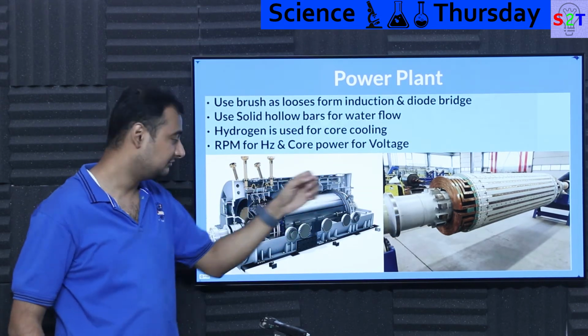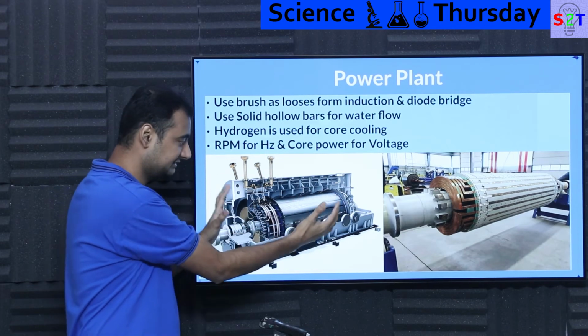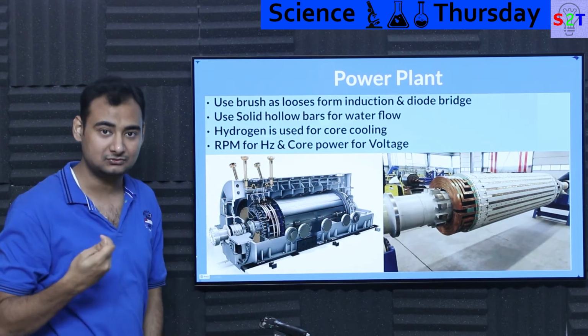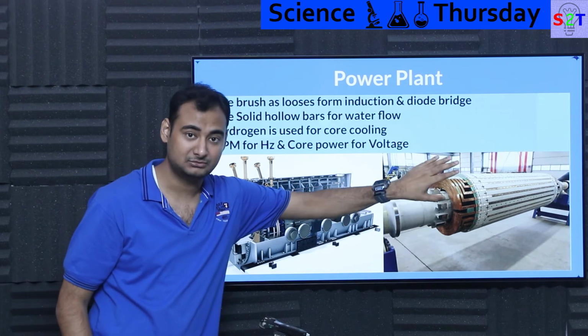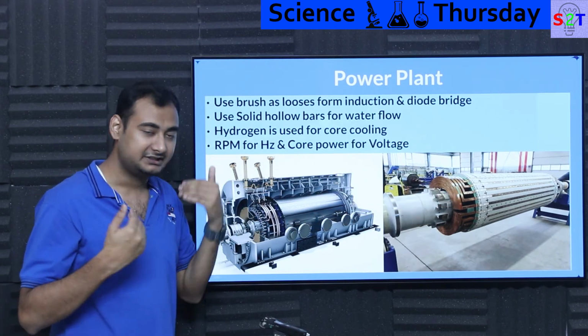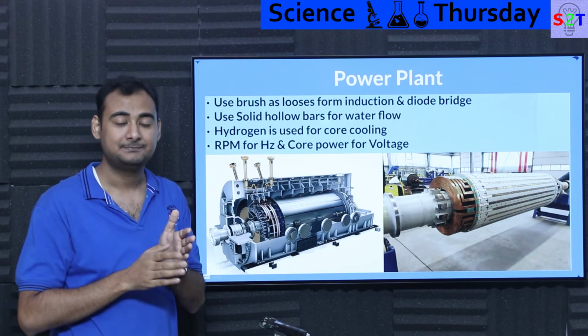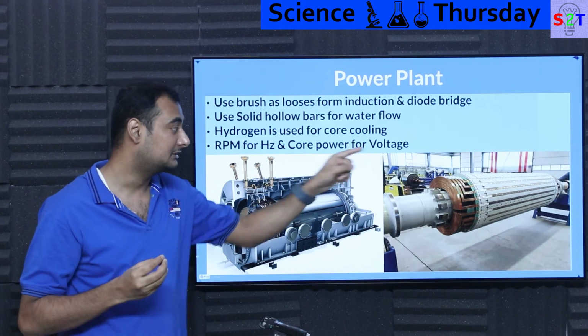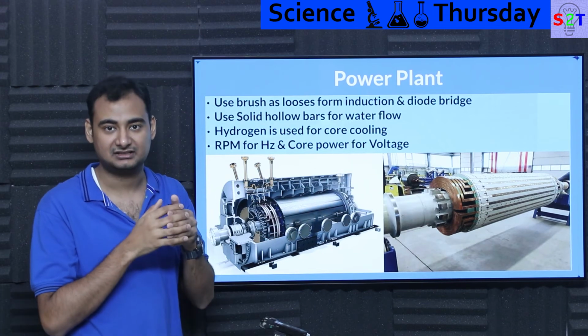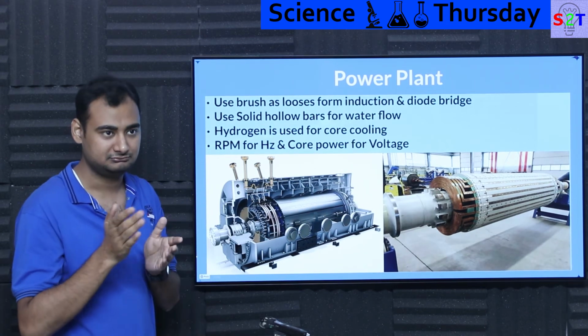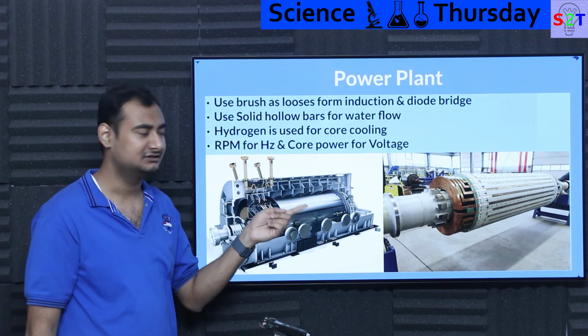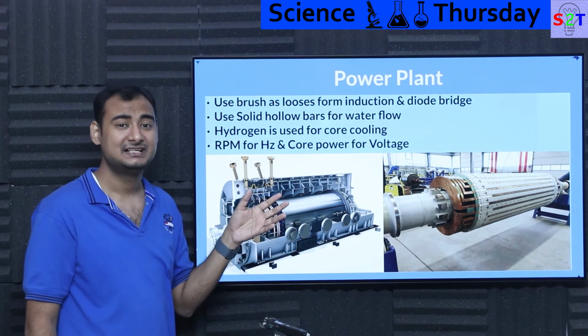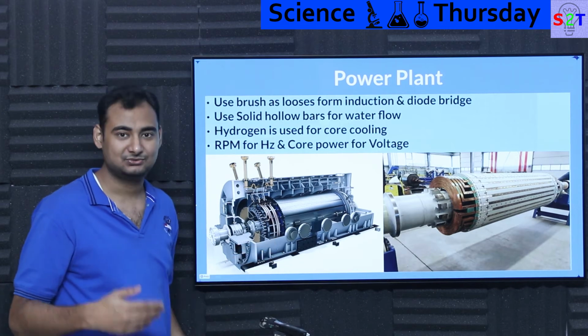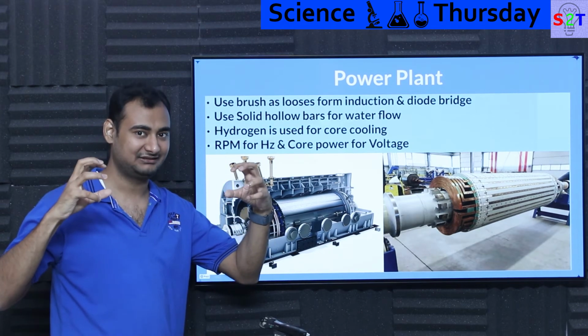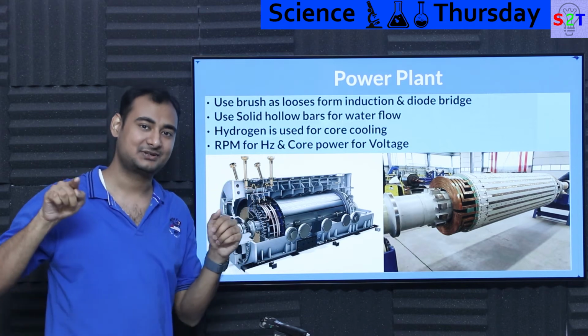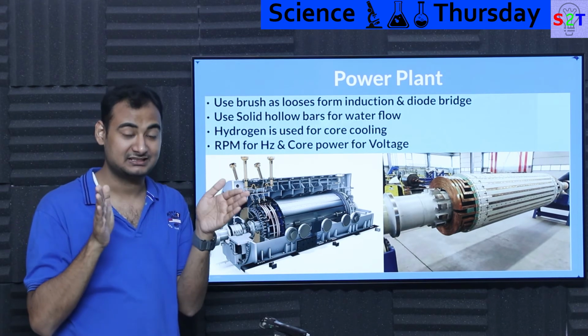So how do you cool the hydrogen? Well, in the rotor casing, basically everything that is encased in the system, there will be water-cooled radiators, and the hydrogen takes the heat away from the rotor and dumps it into the radiator. The radiator is good enough to take the heat away, and that radiator is coupled to this core without any physical connection, utilizing hydrogen as an intermediary step. Hydrogen inside the system is generally around 50 psi to 60 psi, or sometimes even higher, but you do not want too high a pressure, because the bearing seals have to be at an even higher pressure than the hydrogen pressure inside. So hydrogen is completely locked in there.